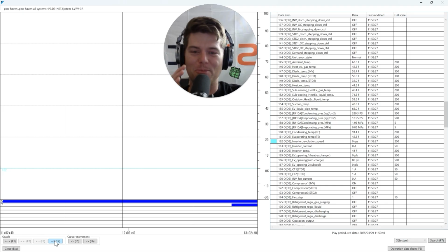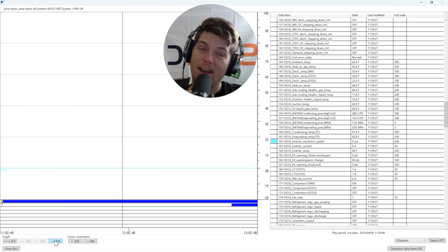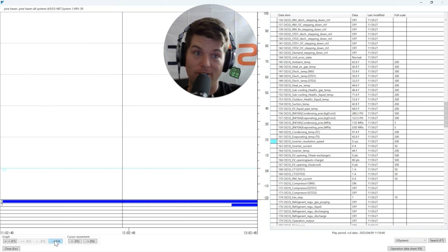And we do this on our preventive maintenances, and my customers and clients always say the same thing. They go, how the heck do you know that compressor is locked out? And I'm like, dude, I looked at 28 hours of data, and that thing never turned on. And it should have turned on like 9 different times. How do I know it's supposed to turn on? Well, because when the system ran up full max and it couldn't meet the actual TC targets, it can't hit the targets.